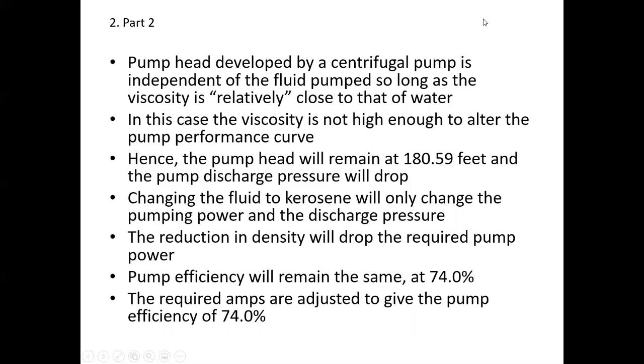I've got a rule of thumb of about a factor of 4 before you really have to get a separate pump curve. Now, if you have enough of a viscosity increase that you're concerned with it, you have to go back to the pump manufacturer, or these days some of the pump selection software online lets you put in a viscosity and, based on the manufacturer's information, modifies the pump curve. But all standard pump curves are put out for standard water, so when you start pumping something else, you have to be concerned that that curve is still going to work for you.